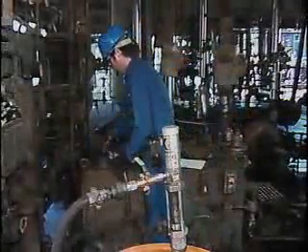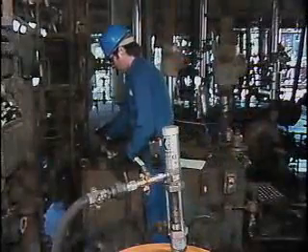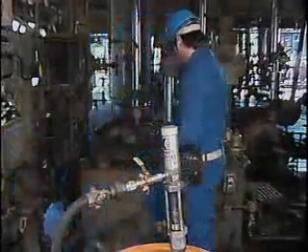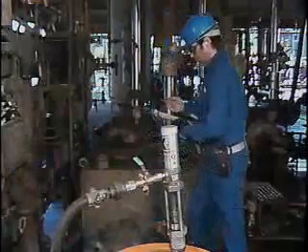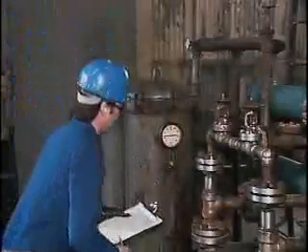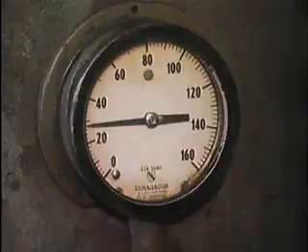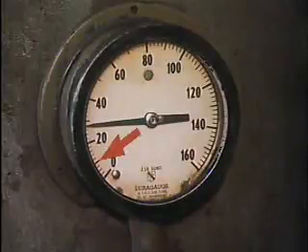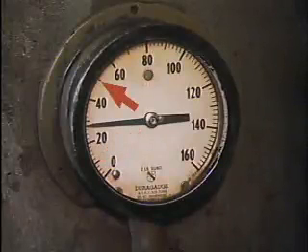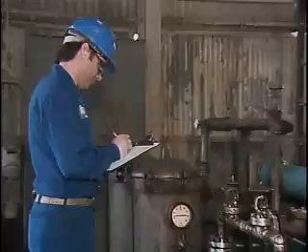It's a good practice to note when oil is added and how much. If oil has to be added frequently, it probably means that an oil leak has developed somewhere in the compressor system. The oil pressure should also be checked. Low oil pressure can be an indication of several possible problems. Low oil pressure may indicate an oil pump malfunction or an oil leak. Higher than normal oil pressure can indicate a clogged filter or blocked oil lines downstream of the gauge.